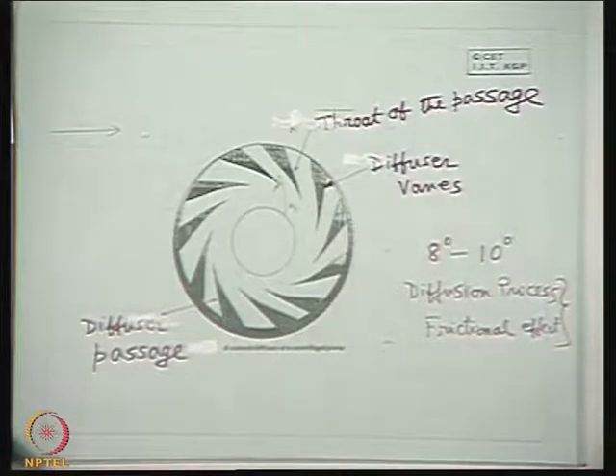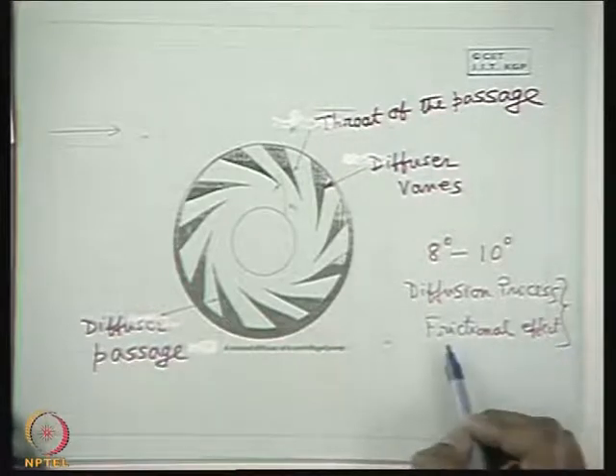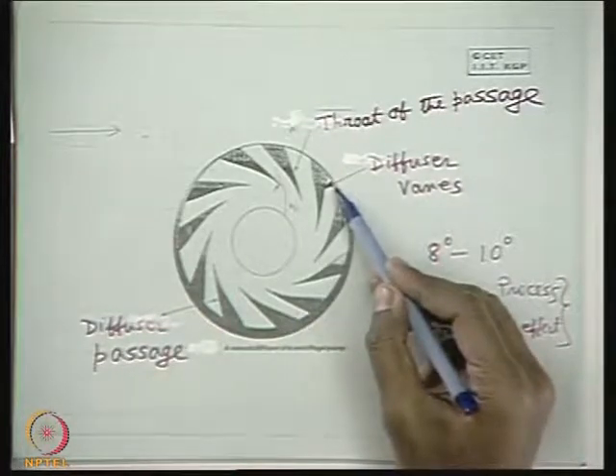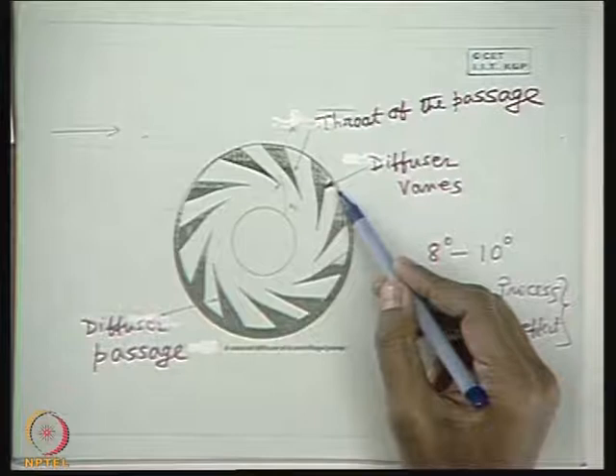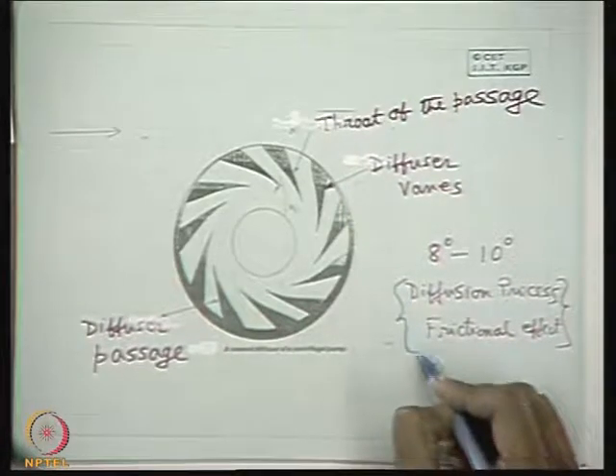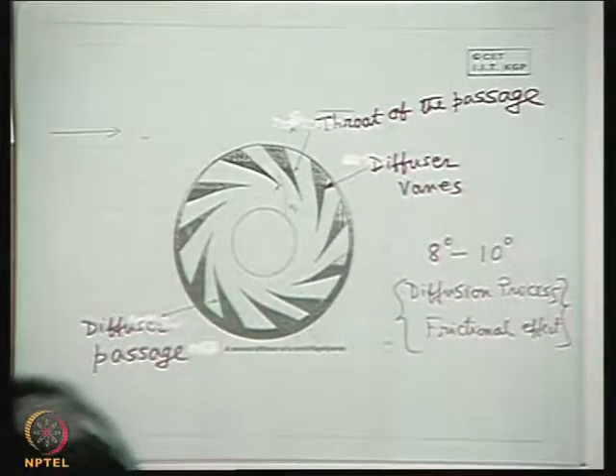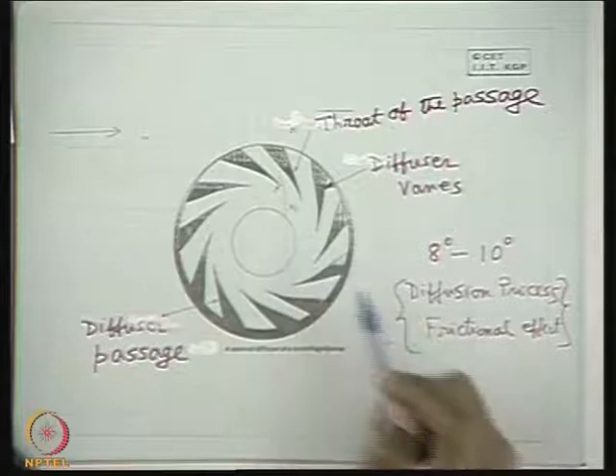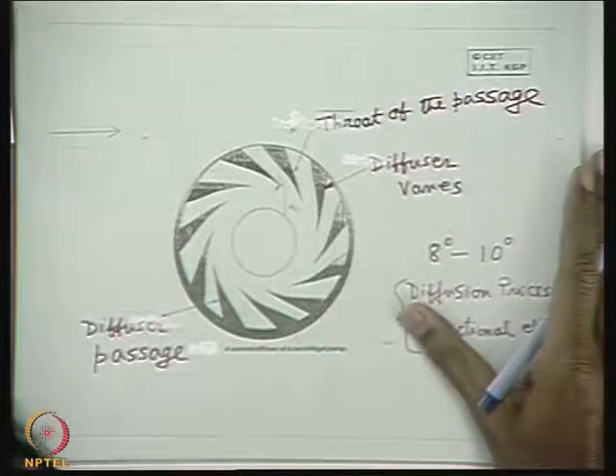If we have more diffuser vanes, the process of diffusion — conversion from kinetic to pressure energy — will be better, but frictional losses will be more. If we have fewer vanes, frictional losses will be less but conversion will not be as effective. These two counteracting phenomena decide the number of vanes. Additionally, the number of diffuser vanes should not have any common factor with the number of impeller vanes, to avoid resonant vibration.